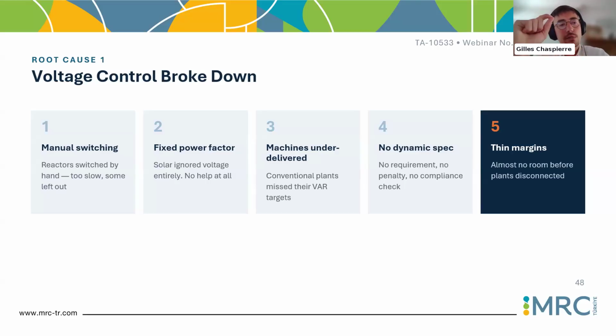But one of the main key messages I would like you to take home is that the root cause of this blackout is really a voltage control aspect. And it's good news, actually, because voltage control means software. It does not mean any additional hardware needed to cope with that. It means that if the voltage control had been better, more dynamic, more able to respond dynamically to voltage variation, maybe this blackout would not have happened at all.